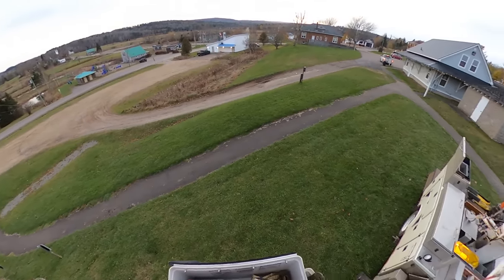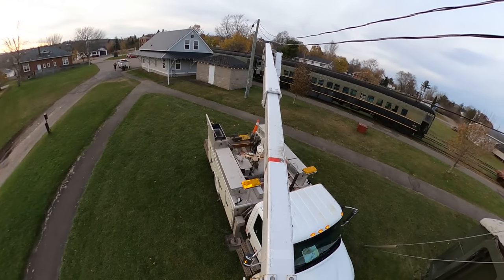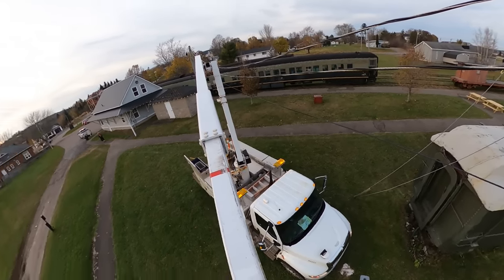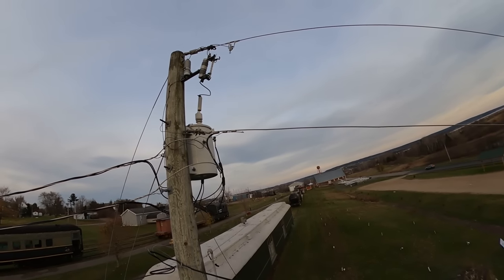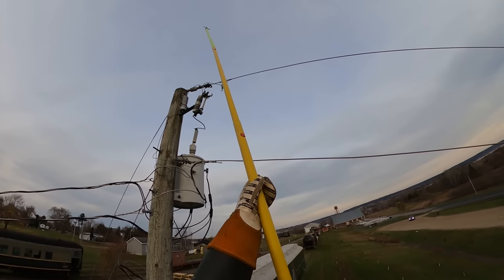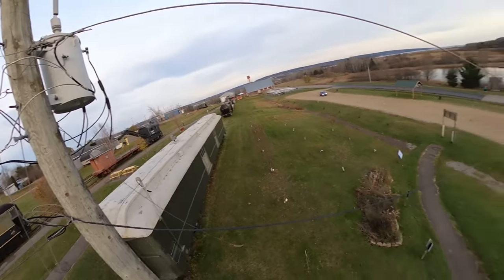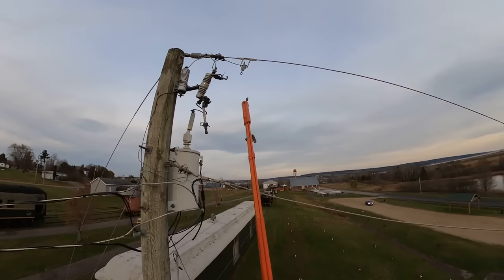The foreman's here now — we had a tailboard and finished loading up material in the truck. The reason I keep looking back at my lower boom is I'm directly below those wires; it wasn't an ideal spot. But if you can get your lower boom straight up and down, you generally don't have to worry too much about it when you're swinging left and right once you're in the work position. I'm trying to get that lower boom all the way up, then I'll use my extension to maneuver in and out near the pole. The first thing we're going to do is open the cutout — even though there's no power flowing through it, we're still going to open it so the top and bottom portions aren't connected as we try and remove that tap clamp.